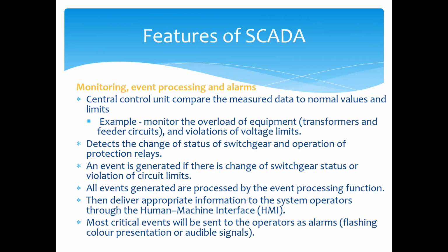So all events generated are processed by the event processing function. Then it delivers appropriate information to the system operators through the human machine interface, HMI. The most critical events will be sent to the operators as alarms, with flashing color representation or audible signals.